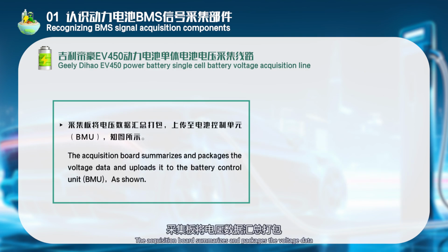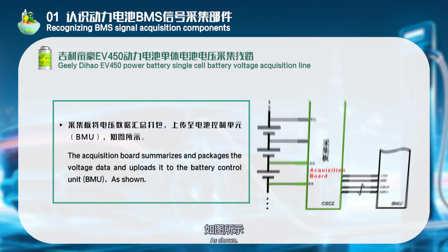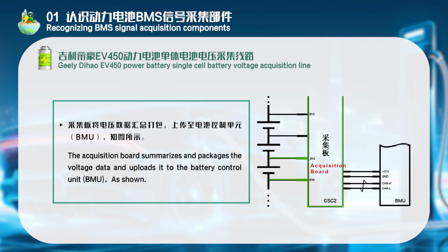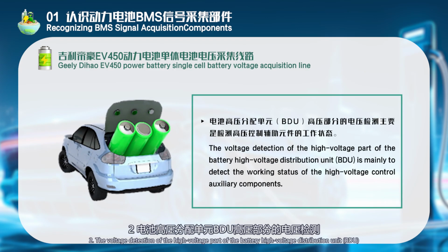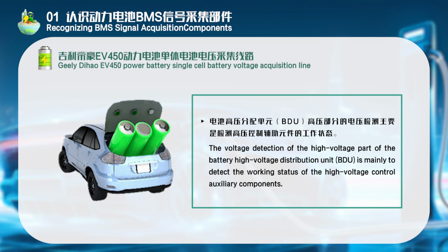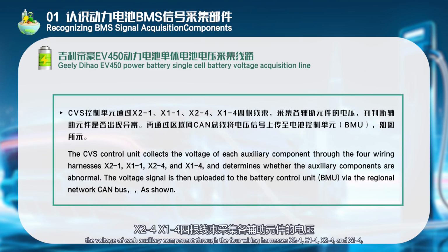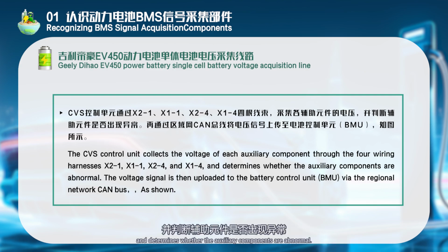The acquisition board summarizes and packages the voltage data and uploads it to the battery control unit BMU, as shown. 2. The voltage detection of the high voltage part of the battery high voltage distribution unit BDU is mainly to detect the working status of the high voltage control auxiliary components. The CVS control unit collects the voltage of each auxiliary component through the 4 wiring harnesses X2-1, X1-1, X2-4, and X1-4, and determines whether the auxiliary components are abnormal. The voltage signal is then uploaded to the battery control unit BMU via the controller area network CAN bus, as shown.